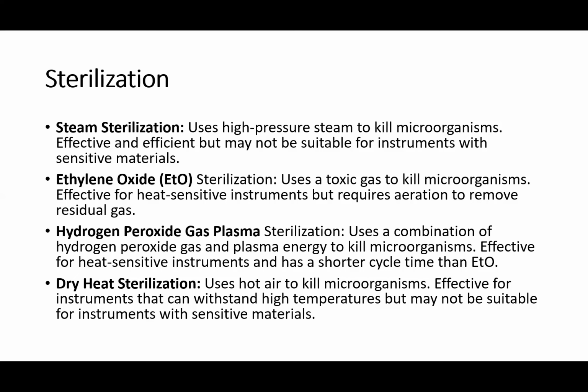Then ethylene oxide sterilization uses toxic gas to kill microorganisms, effective for heat sensitive instruments, but it requires aeration to remove residual gas. Now, there are specific devices that are used for aeration after exposing this instrument to ethylene oxide gas. Hydrogen peroxide gas plasma sterilization uses a combination of hydrogen peroxide gas and plasma energy to kill microorganisms. Now, effective for heat-sensitive instruments and has shorter cycle time than ethylene oxide gas. Then dry heat sterilization uses hot air to kill microorganisms.